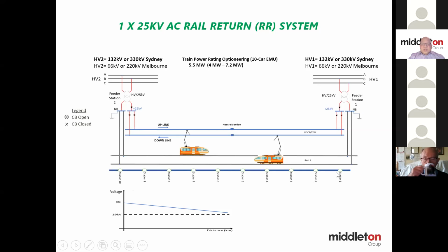So obviously the train will have to stop at every station and in both directions. The voltage drop on the system, if I just show you half the system, will drop virtually linearly. But of course, your design needs to meet standards. So for a good system, you want to make sure that it meets the 19 kV permanent voltage. And of course, in addition, there is the mean useful voltage that you need to meet as well, which is 22.5 kV, which is the average voltage.